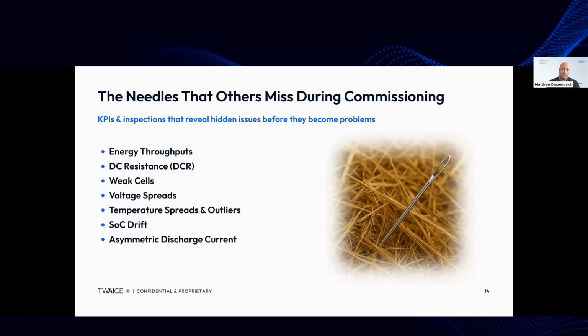Another interesting thing we tend to see relates more to the actual data side of this, SOC drift and asymmetric discharge current. We'd expect that a brand new system is able to discharge all components at the same rate, and that you'd see more of a linear SOC curve as you're going through charge and discharge, but we oftentimes see quite a few anomalies in that data, which can be addressed earlier on.